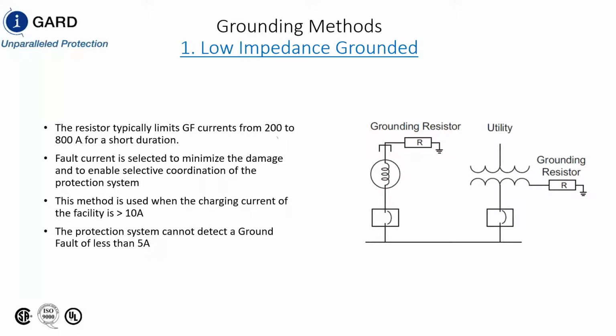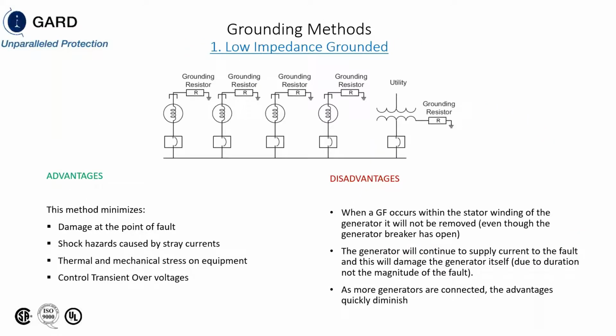You still want to limit the fault current to a low value. So this is the typical scheme we have for a low resistance grounded system and a medium voltage bus connected generator system. So when you have multiple sources and each one has a low resistance grounded system, you have damage at the point of the fault. In this particular case, if each resistor was limited to 400 amps for 10 seconds, you're going to have 2,000 amps of fault current in that fault if all the generators are connected.